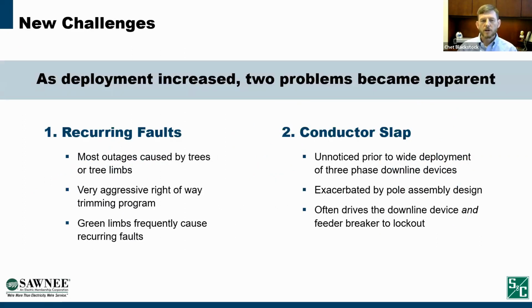So since then, we've deployed over 500 Interrupters, but as we deployed more and more, two problems started to occur. The first was these reoccurring faults. Since most of our outages are caused by trees, even though we have an aggressive right-of-way trimming program. I noticed in the poll that that was the solution that seems to be most frequently deployed, is to have aggressive right-of-way trimming, and we do that. But we still get a lot of green trees falling from outside the right-of-way and limbs breaking off during storms and falling on our lines. And those green limbs frequently cause recurring faults.